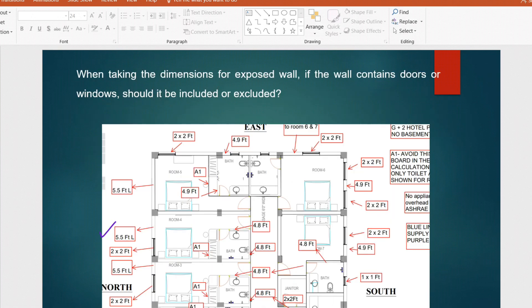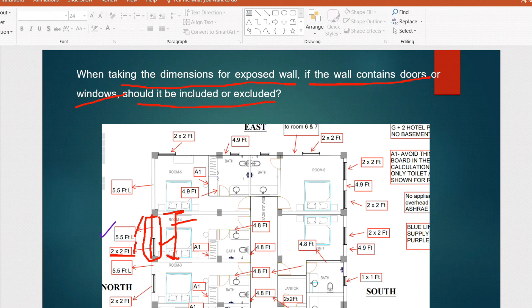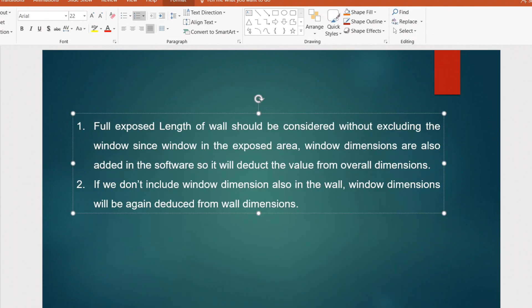The next question is related to HAP cooling load calculation: when taking the dimension for an exposed wall, if the wall contains a door or window, should it be included or excluded? For example, for a room with an exposed wall of 5.5 feet total length that contains a 2×2 foot window — when entering the exposure wall length in HAP, should I include the full 5.5 feet or only the solid wall portion? The answer: the full exposure length of the wall must be included without excluding the window.